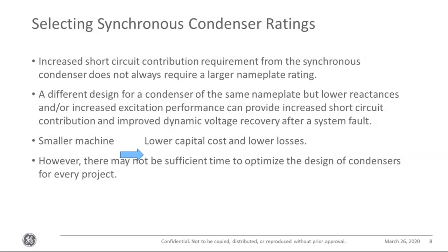So the point is that you could have a smaller rated machine with a smaller reactance and smaller subtransient reactance give equivalent or sometimes even better short circuit contribution as a larger nameplate machine, but a larger reactance, right? And also likewise, if you want to improve the dynamic voltage recovery, you could try designing your condenser appropriately with smaller reactances, perhaps smaller time constants, or more aggressive excitation systems, increased field forcing limits, or using static excitation systems, and so on and so forth. So you don't always need a larger machine.